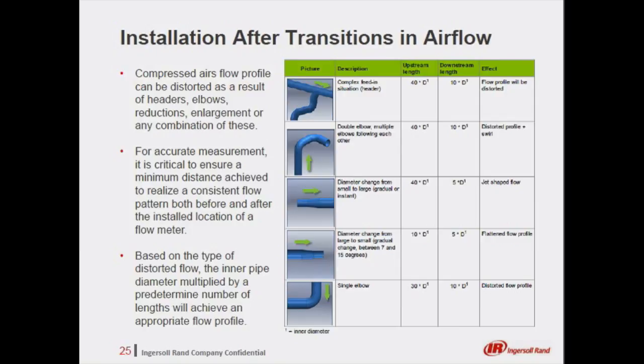For example, a change in diameter from small to large in a 6-inch header pipe would recommend 40 lengths upstream and 5 lengths downstream. The 40 lengths of 6-inch pipe equates to 240 inches or 20 feet upstream and 30 inches downstream. Airscout inlines come standard with inlet and outlet piping. These accessories are typically all that is required to obtain accurate measurements. No additional length of pipe from transition point is typically needed.